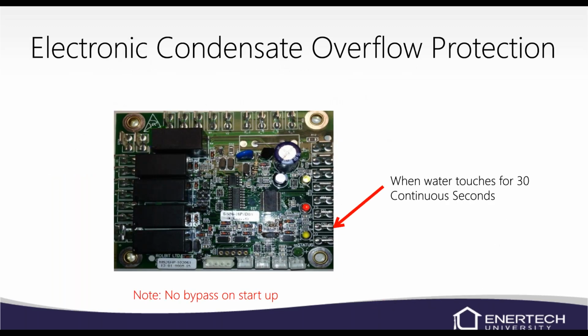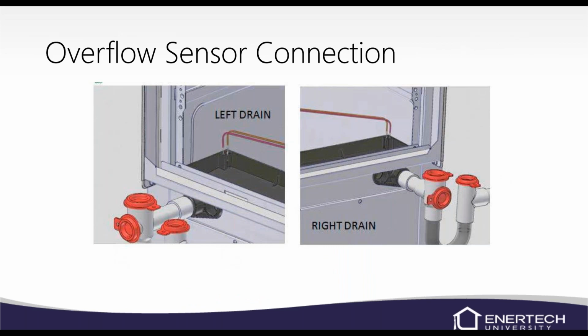The condensate overflow, they're the 2 terminals here, and there's no bypass on startup, and it has to be open for 30 seconds. On the condensate overflow, on the older style units, an XT or a CT packaged unit, the sensor for the drain can go either on the left side or the right side. We prefer that wherever you pipe in your drain, whether that's left or right, that you would move that sensor to the other side, and it'll sense better. You may get a premature fault if you leave it on the same side. It's not going to be the end of the world. The unit will still run. It's just when you get a little bit higher water in that pan that you can get a fault. So we try to get that switched over.